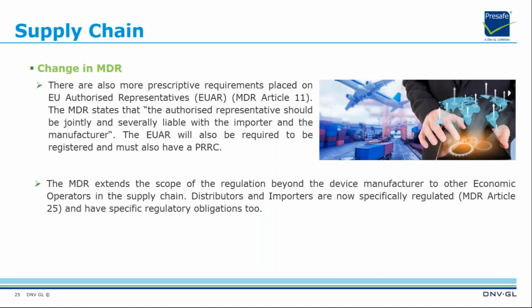The next change is about the supply chain. We have so many changes in supply chains. There are also more prescriptive requirements for the EU authorized representative, called EUAR, based on Article 11. The MDR states that the authorized representative should be jointly and severally liable with the importer and the manufacturer. The EUAR will also be required to be registered and must also have a PRRC. So authorized representatives have to have a person responsible for regulatory compliance.